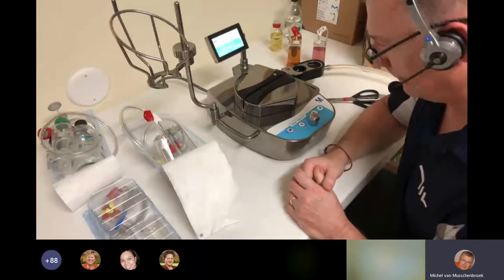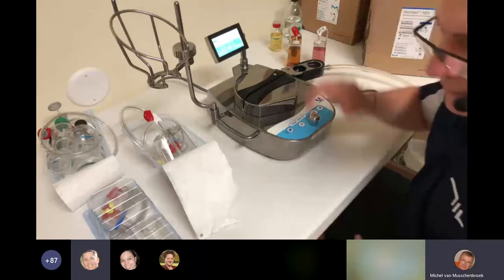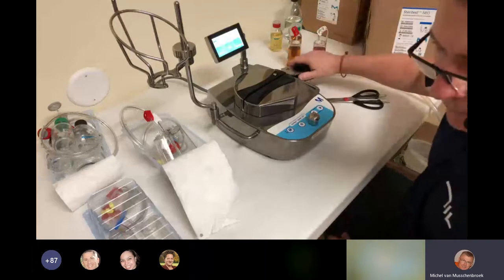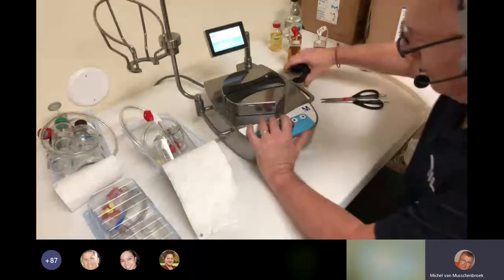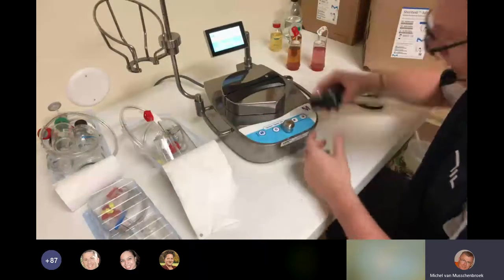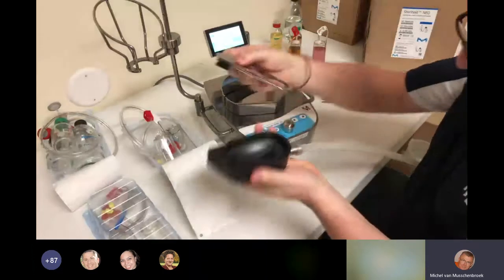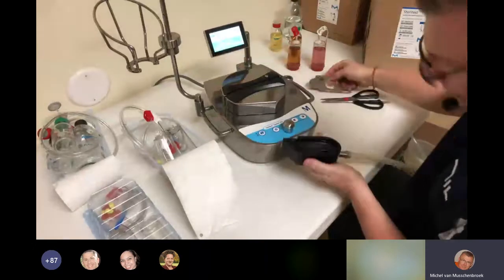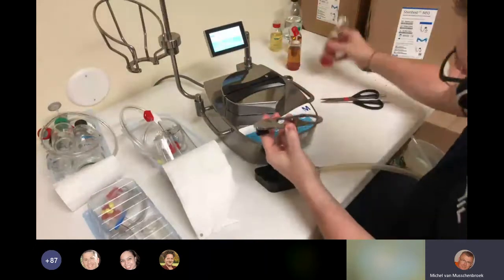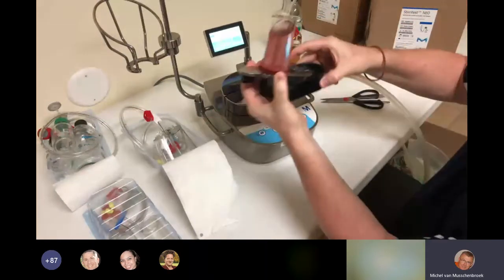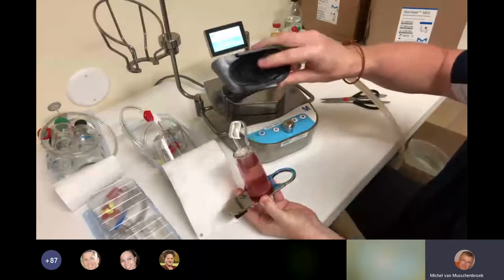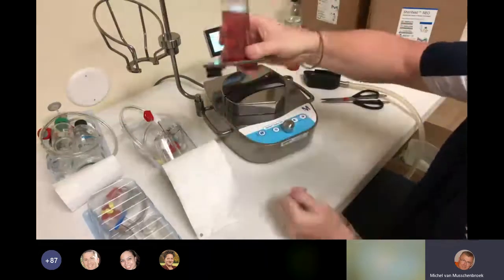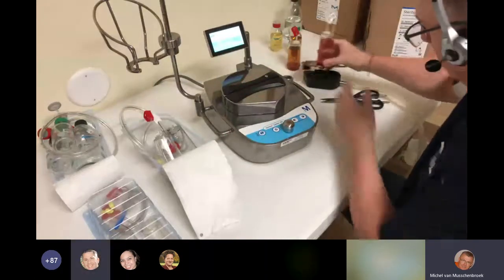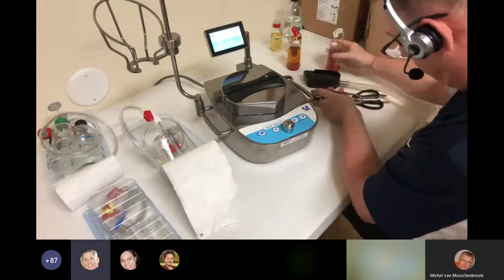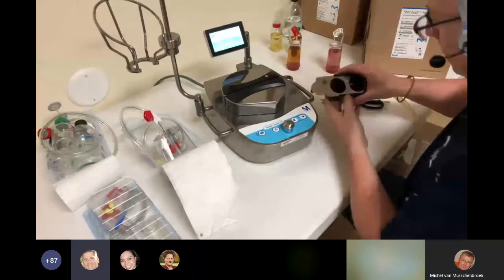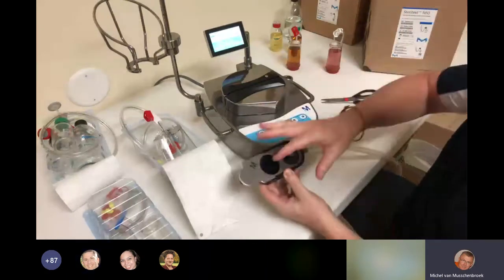Hey, Michelle, is it necessary to autoclave the black drain tray to avoid contamination? It's not necessary. It's downstream, but if you want to make that part of your standard cleaning procedure, there's no reason why you can't. As I said, the unit is downstream. It comes off pretty easily, and you can see there is a gap. Here's how the canister sits in, and there's a gap between it and the base. So there's liquid down here, but there's no chance of it coming up into the bottom of your canister. Also, that redesigned drain tray was designed to eliminate or reduce as much as possible splashing from any filtration. Correct. Yeah, it's nice and rounded with a channel down the middle.